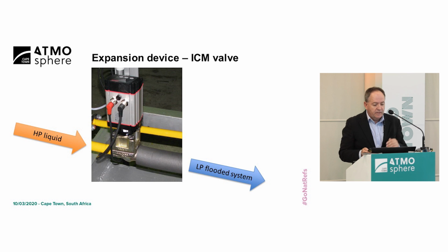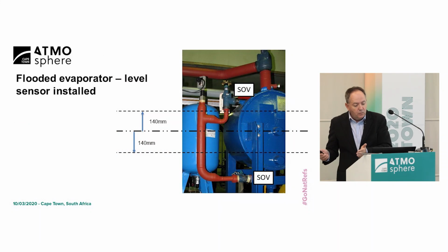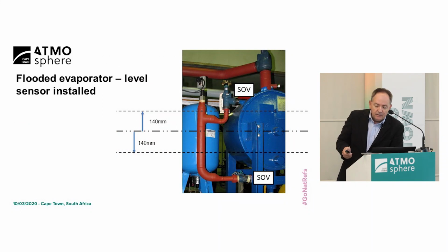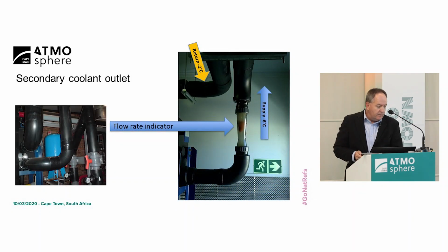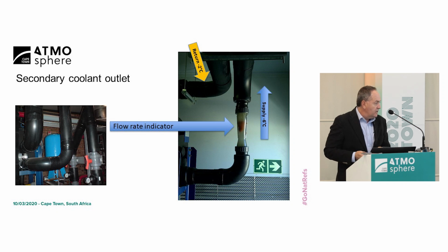Oil drain with a dead man's valve. In this case, we didn't do automatic oil return. There's the ICM valve, so that's your expansion device, with high pressure liquid on the one side, feeding liquid into your expansion device. That's just a little bit clearer, but basically you want to maintain that level in the heat exchanger. A handy feature is a flow meter, very handy if you have a secondary cooling system.